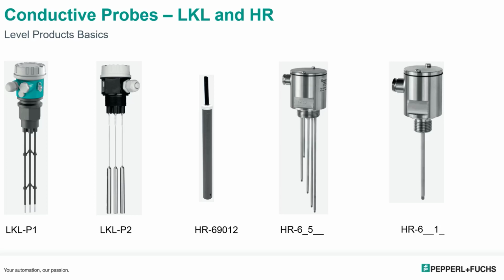And you can get up to 5-point control on this. So you can have 5 rods or 5 cables coming down. Obviously, if you're using 5-point control, the tank must be metal so that you can get your signal back from the conductivity of the liquid, because it basically has to have a path for the electricity to go through. So for cement tanks, if you have 5 electrodes, you can only have 4-point control. If it's a metal tank and you can use that as your ground reference, then a 5 probe can have 5-point control. The HR 69012 is a single-point conductive probe used for deep wells.